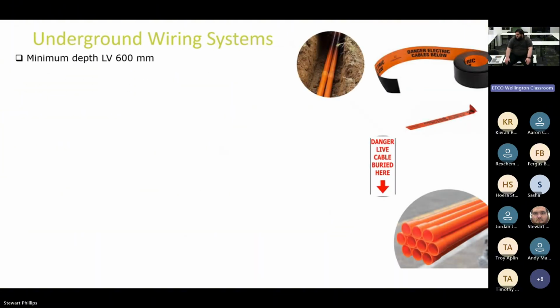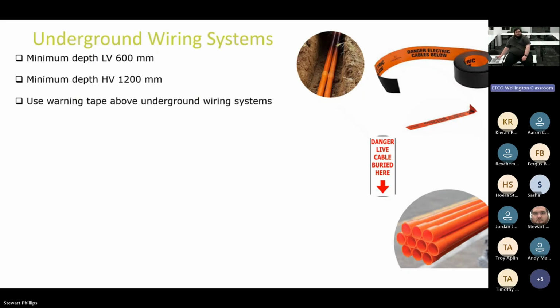So, minimum depth for low voltage, 600 mil. So that's to the bottom of the trench. The minimum depth of cover is 500, but to get to that, we need to dig down to 600. Minimum depth for high voltage is 1200. We need to use warning tape above underground wiring systems.